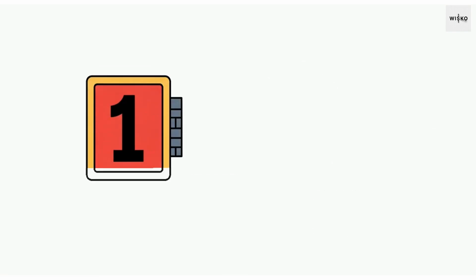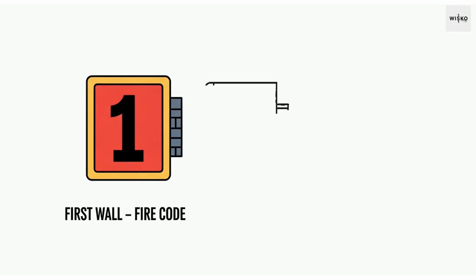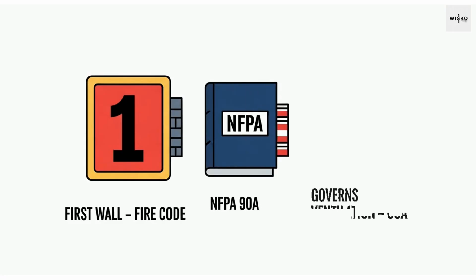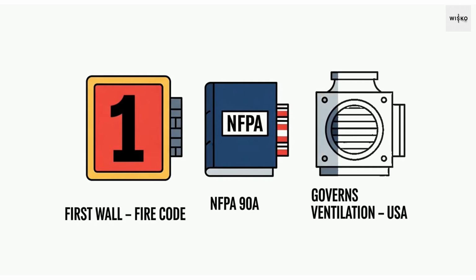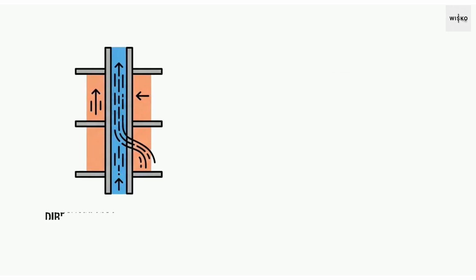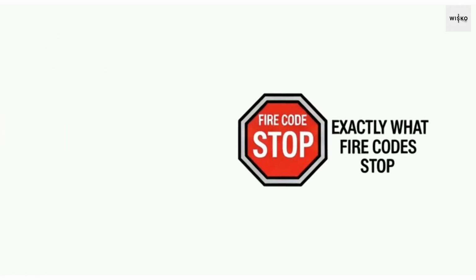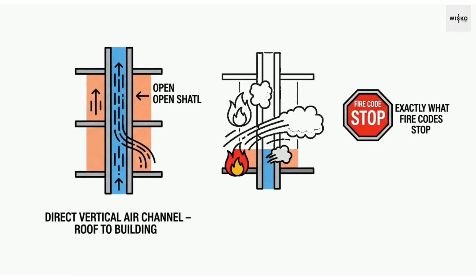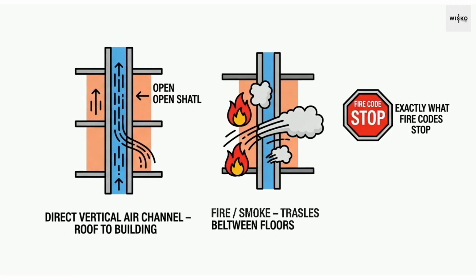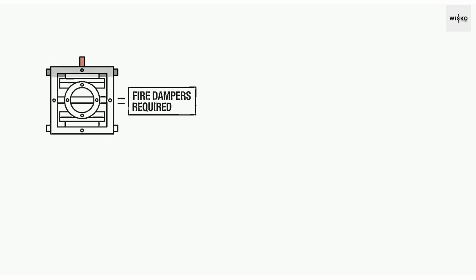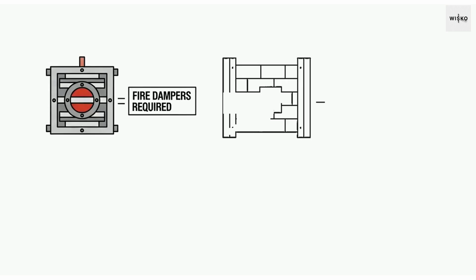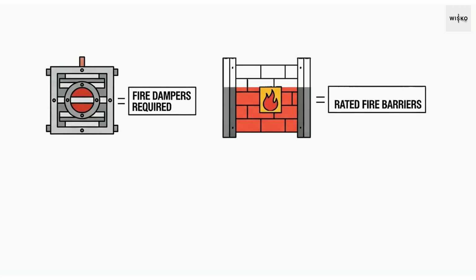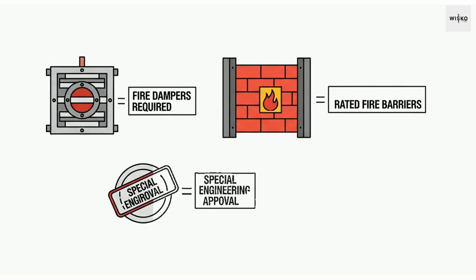The first wall is fire code, specifically standards like NFPA 90A, which govern ventilation systems in the United States. A windcatcher creates a direct vertical air channel from the roof straight into the building, and that's exactly what fire codes are designed to stop, because an open shaft like that can let fire and smoke travel rapidly between floors. Building that legally now requires fire dampers, rated fire barriers, and special engineering approval, turning a simple ancient tower into an expensive compliance project.